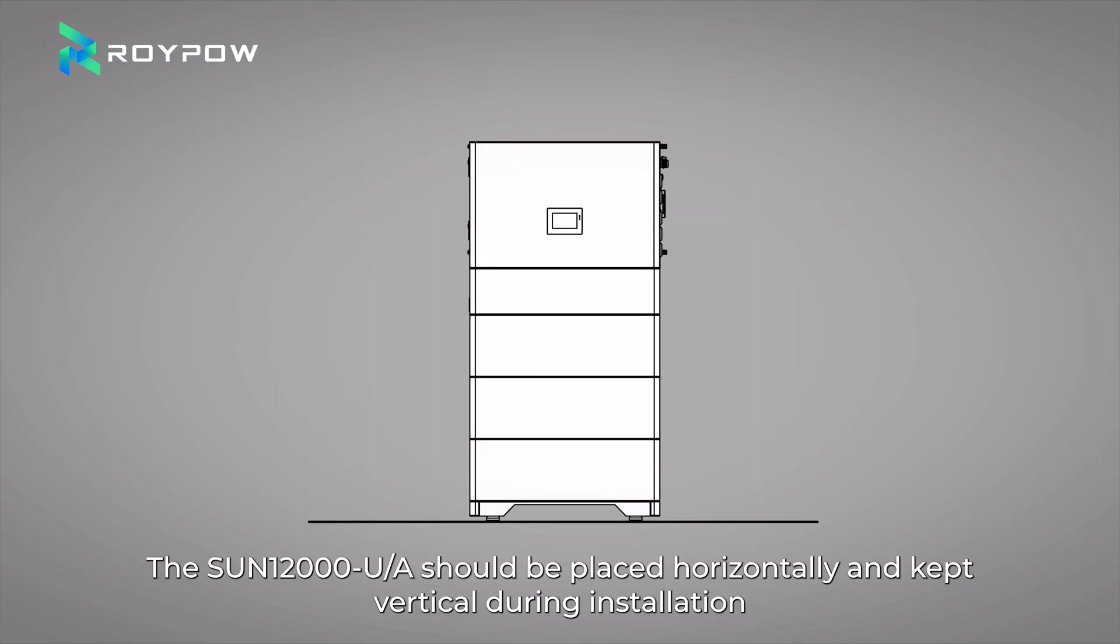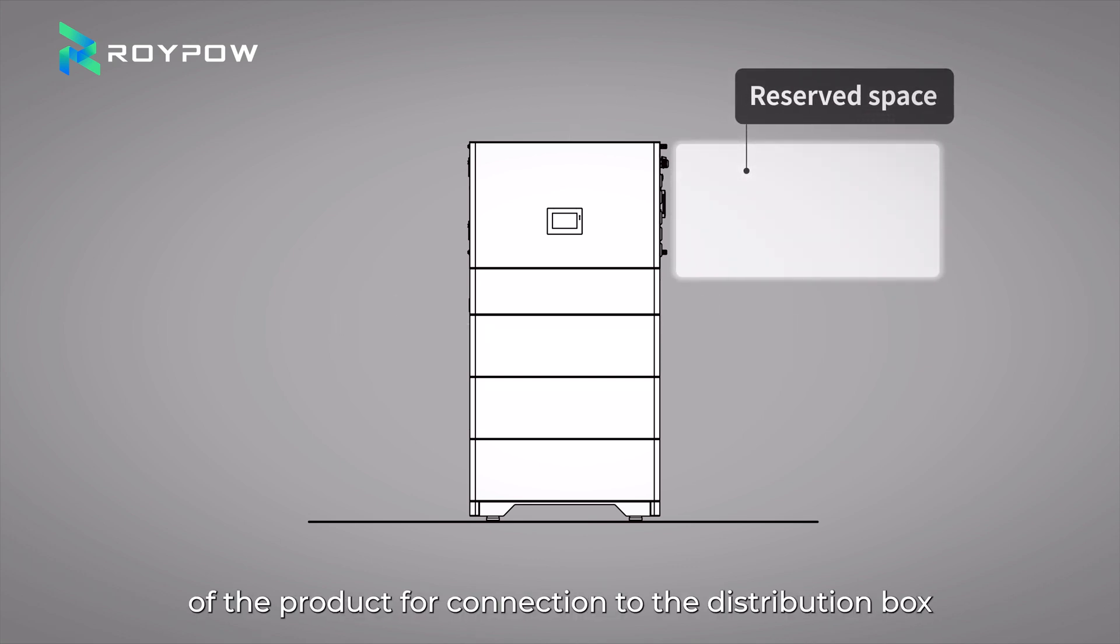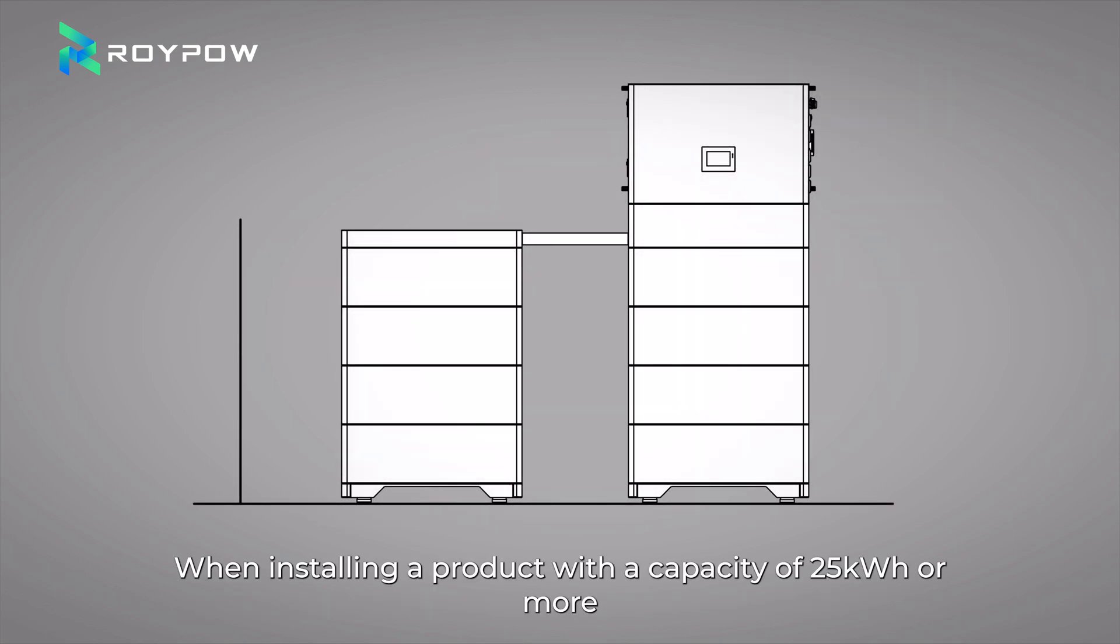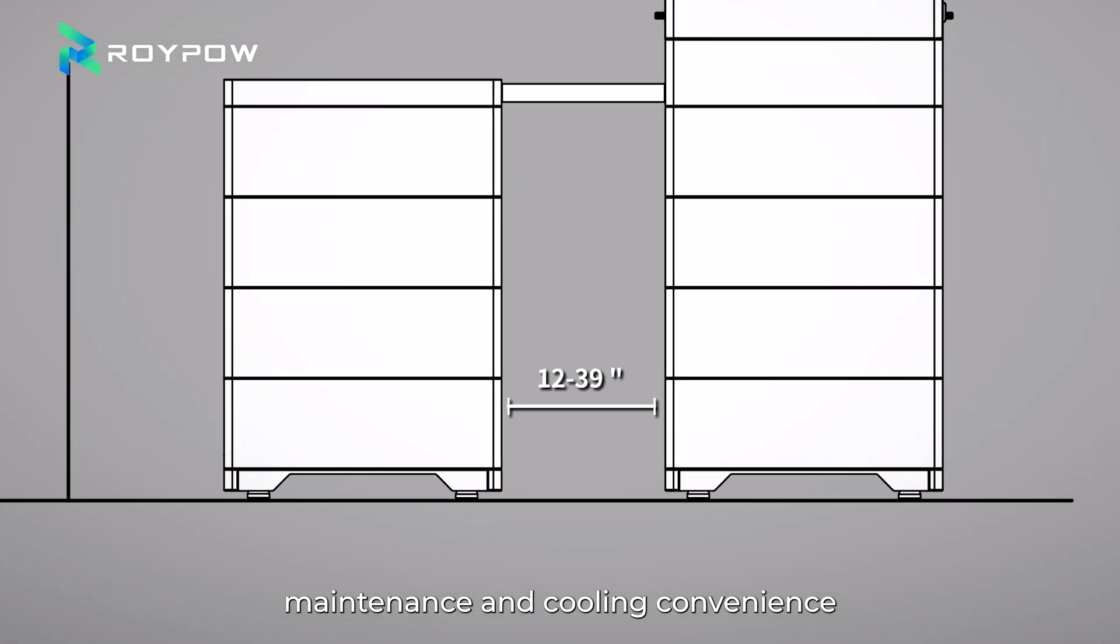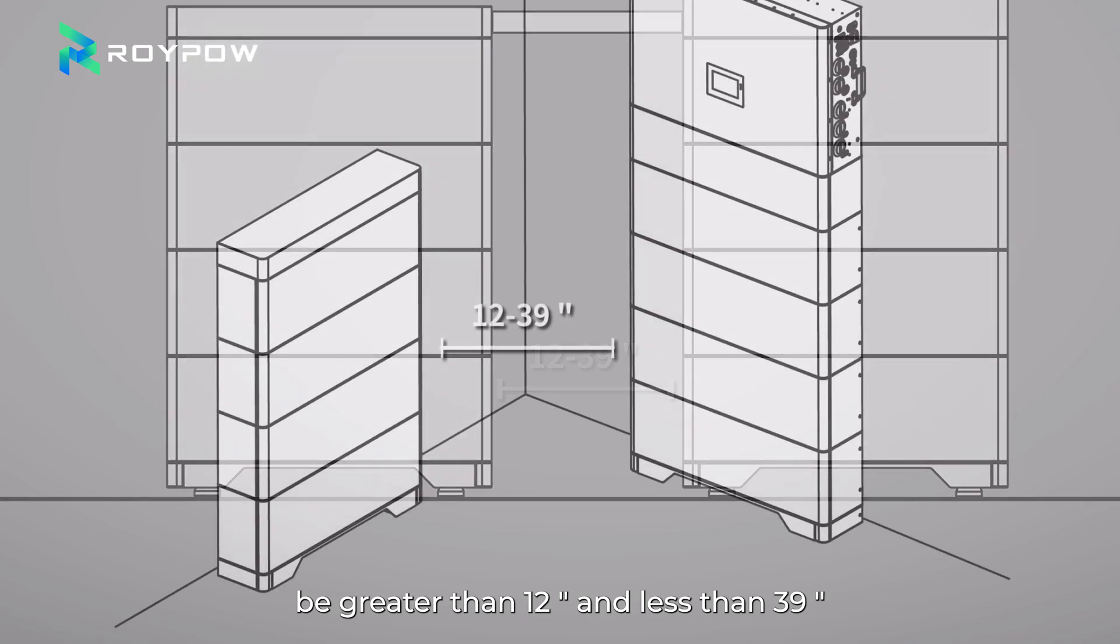The 12kW 15kWh System should be placed horizontally and kept vertical during installation. Maintain at least a 12-inch clearance on the left, right, and top sides of the product to ensure adequate ventilation for cooling. Ensure there is enough space on the right side of the product for connection to the distribution box. When installing a product with a capacity of 25kWh or more, install it in double tower. For installation, maintenance, and cooling convenience, it is recommended that the clearance between battery clusters be greater than 12 inch and less than 39 inch.